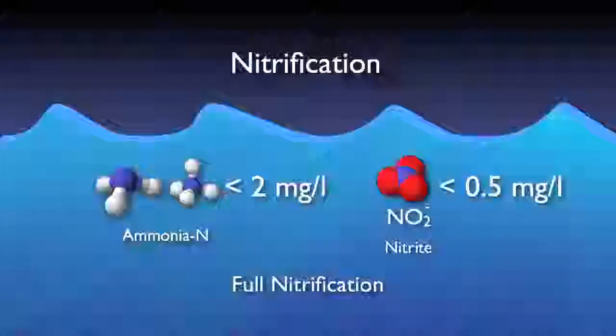As mentioned, nitrification is a very oxygen-hungry process. As a comparison, in order to remove 1 pound of BOD, 1.2 pounds of oxygen are required. However, to reduce 1 pound of ammonia to nitrate, 4.6 pounds of oxygen are required.